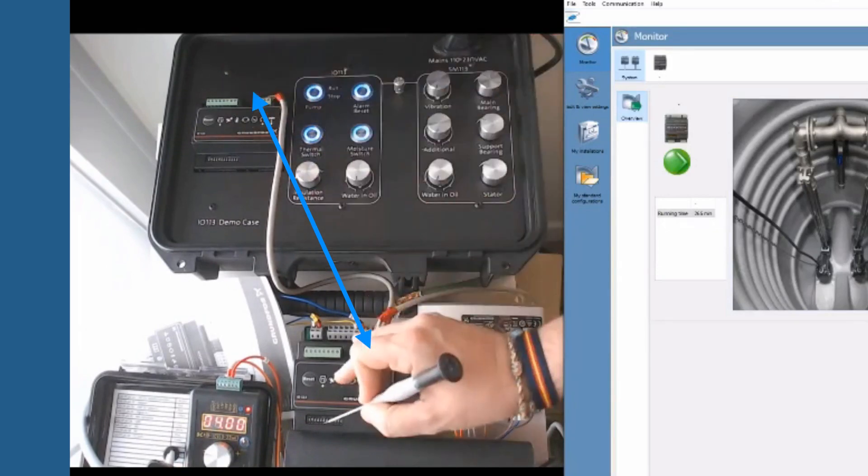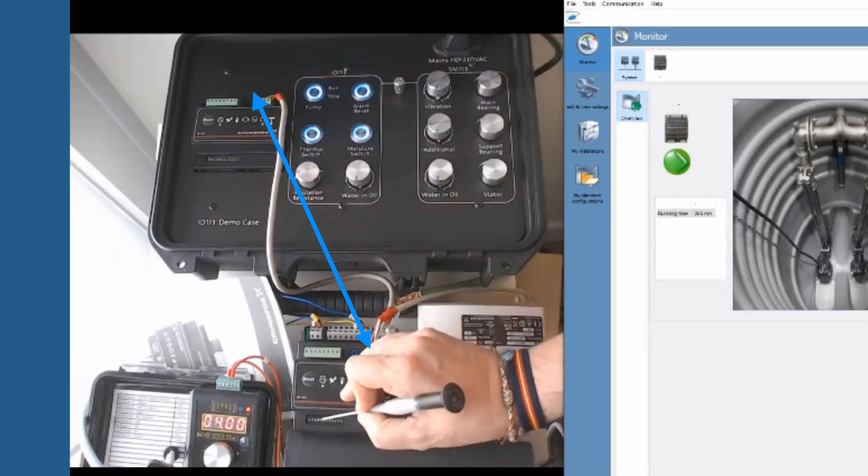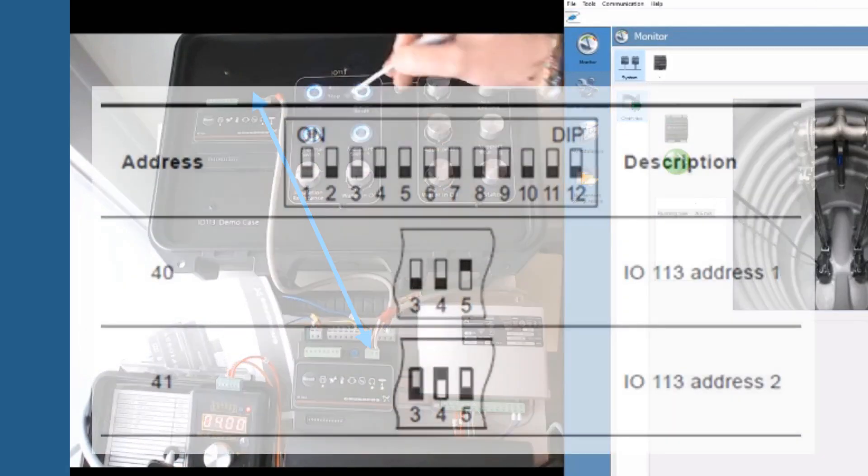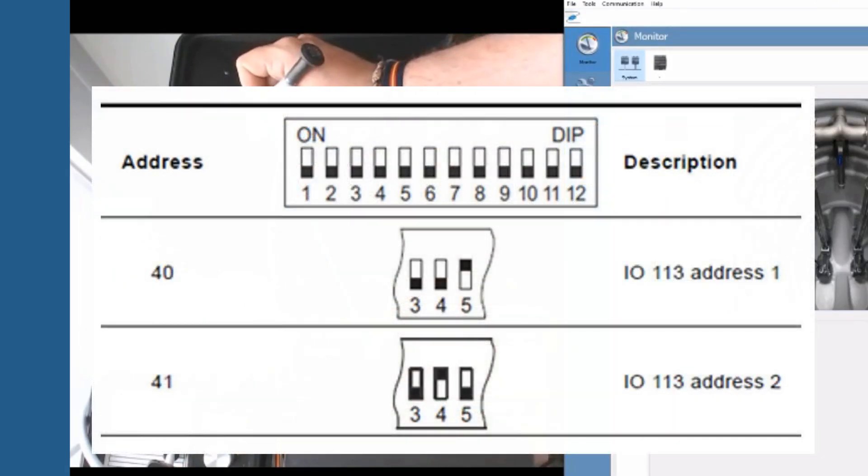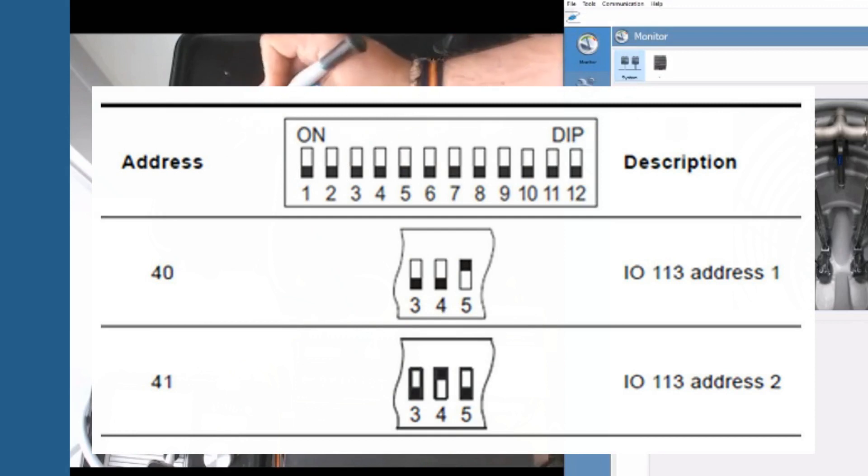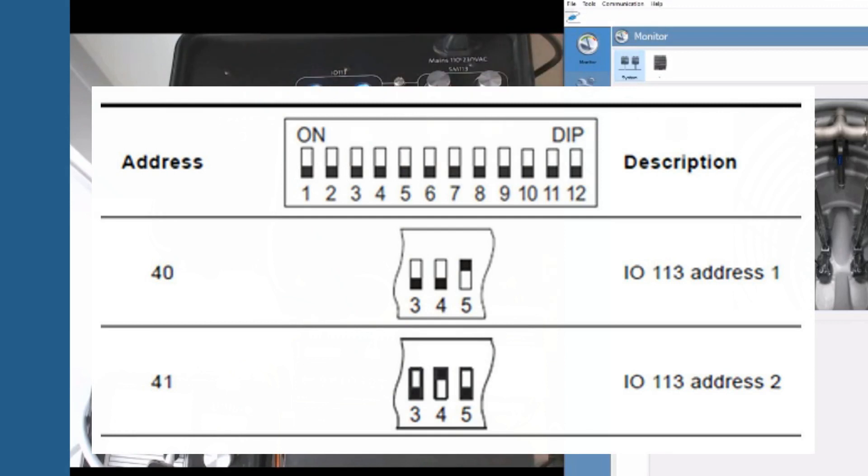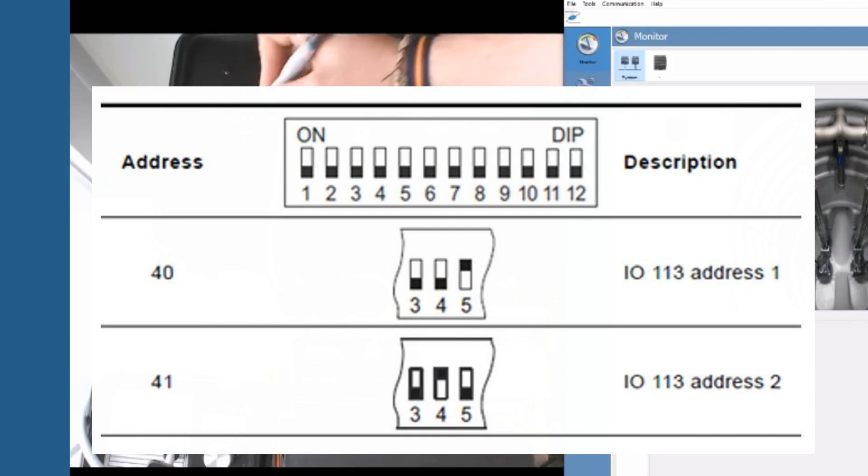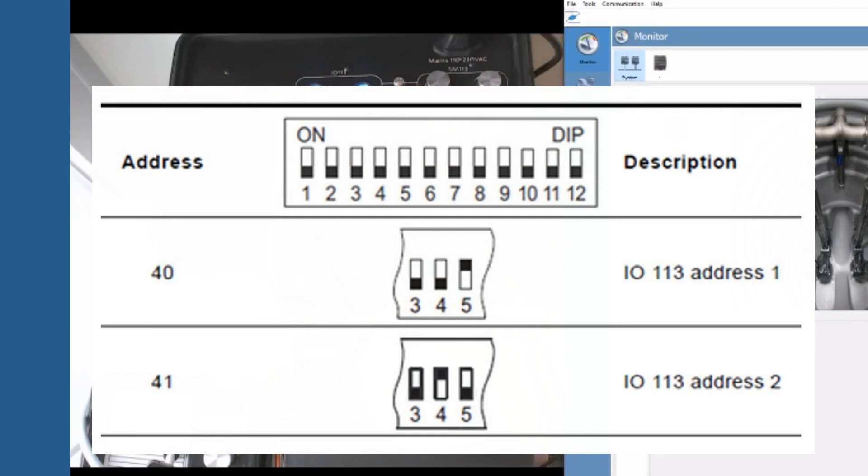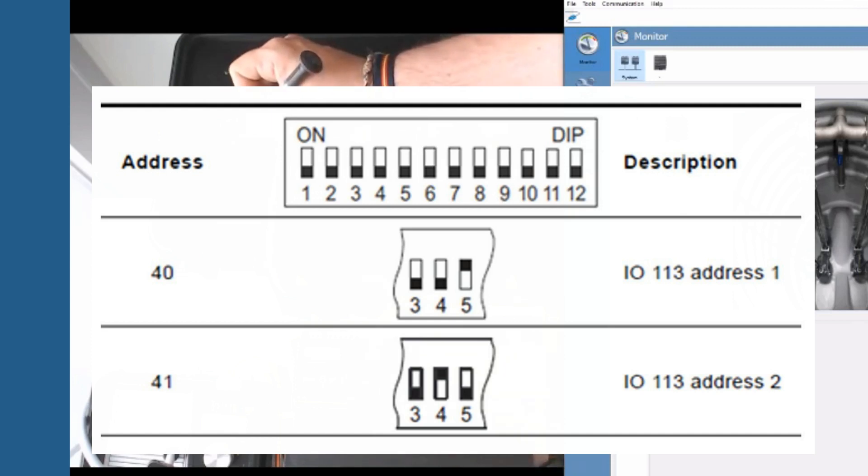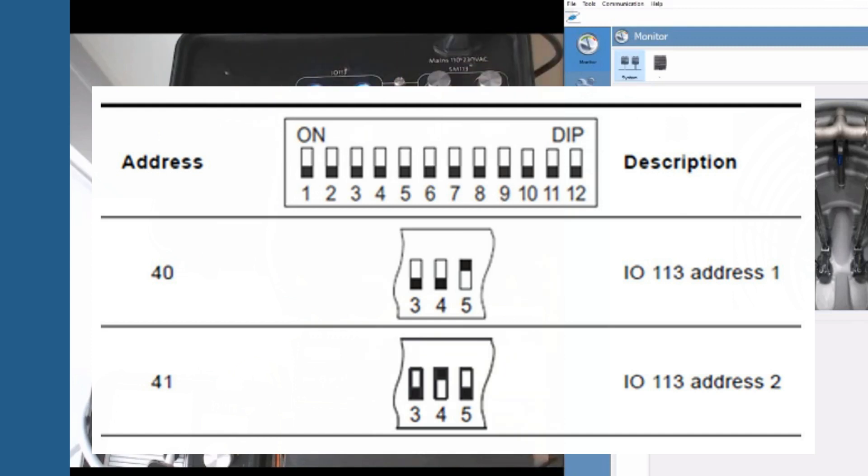Then change the DIP's position depending on protocol and the position of pumps in the network. We will set the DIPs 3, 4 and 5. If more than one pair of IO-113 and SM-113 are used in the control system, make sure that address settings are handled pair by pair.